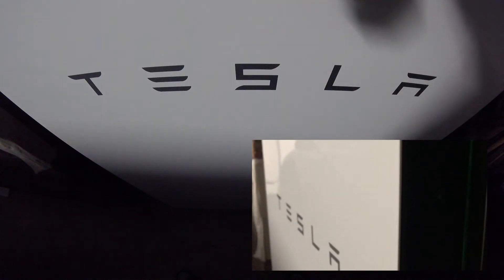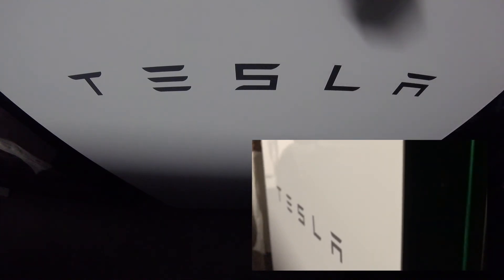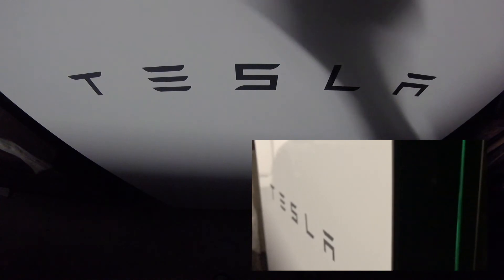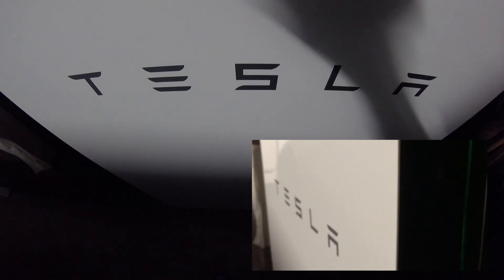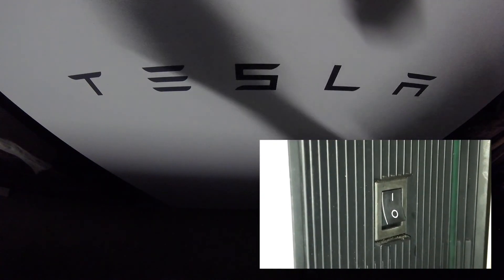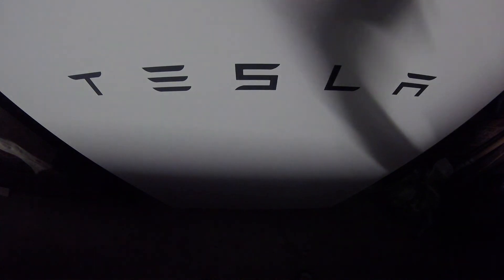On the side of the Powerwall — and I'll show a video of this — there is a green bar which indicates whether it's charging, discharging, or idle. Apparently this green bar of light has to be switched off completely; that's how you know it's basically turned off. You wait for that bar to turn black, which takes about 5 to 10 minutes. When it's dark, switch the circuit breaker back on, and also the Powerwall itself back on. So that's what I did, and it switched on after 10 minutes, and everything's working fine again.